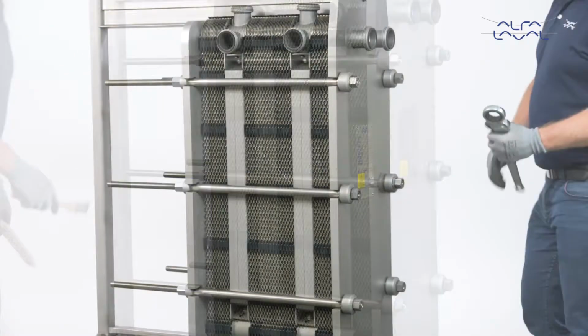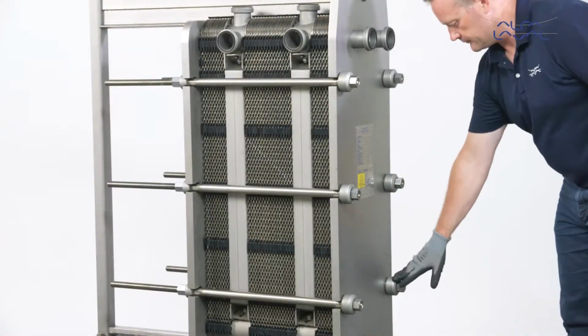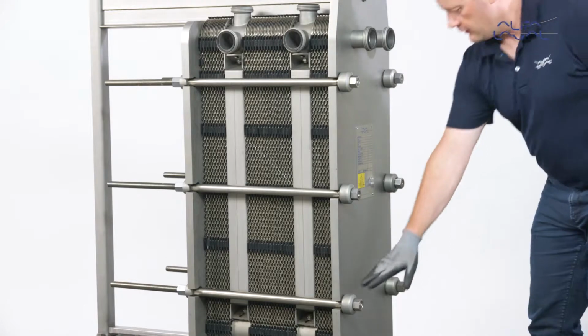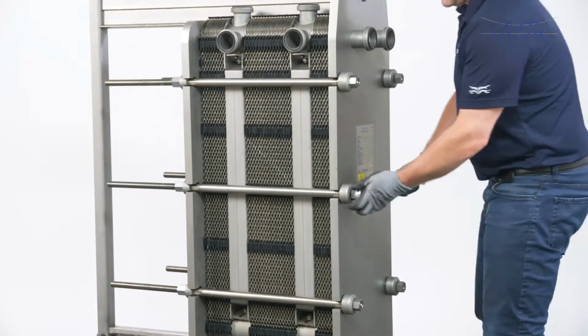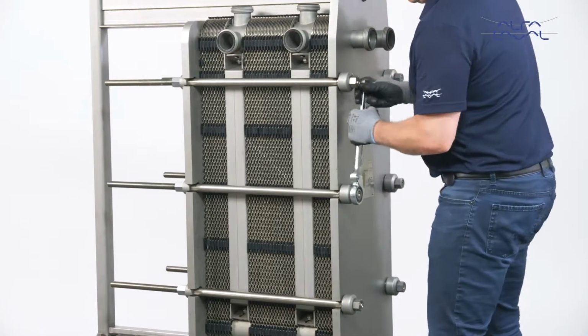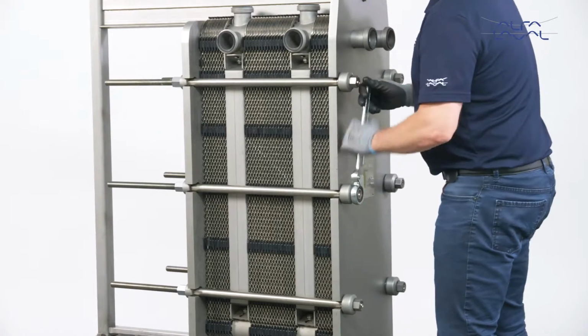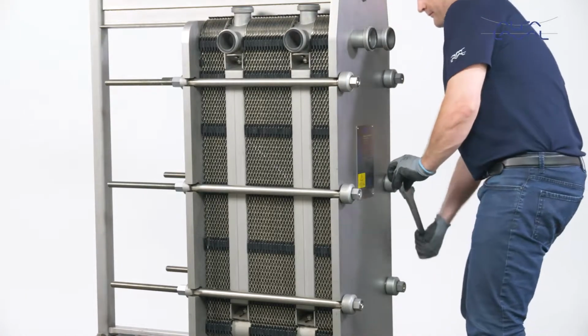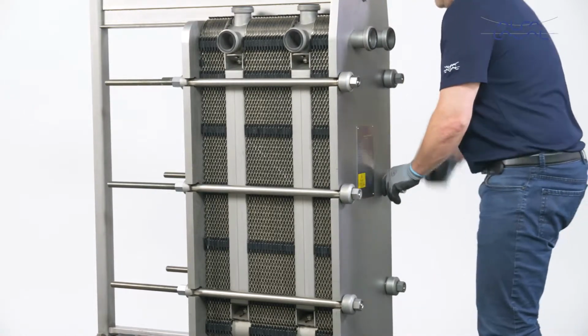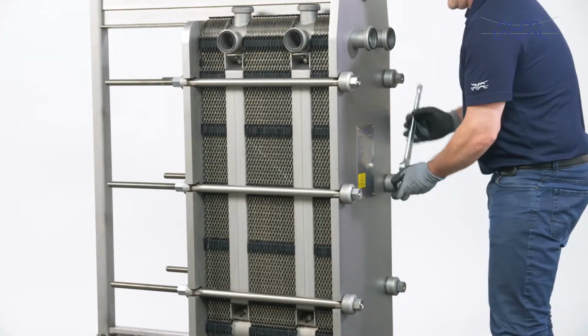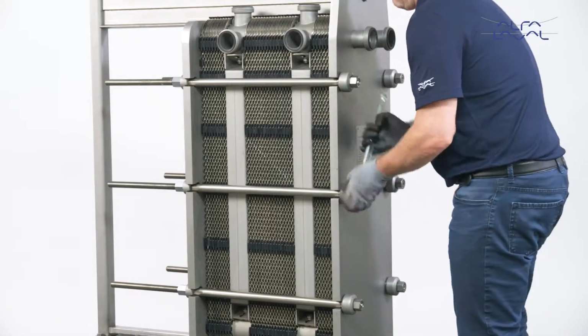There are 4 main tightening bolts on smaller units, which are equipped with a bearing box. All other bolts are referred to as locking bolts. Now, start by loosening the locking bolts in the middle of the plates. Smaller units will have locking bolts at the top and bottom. These should be loosened and removed.